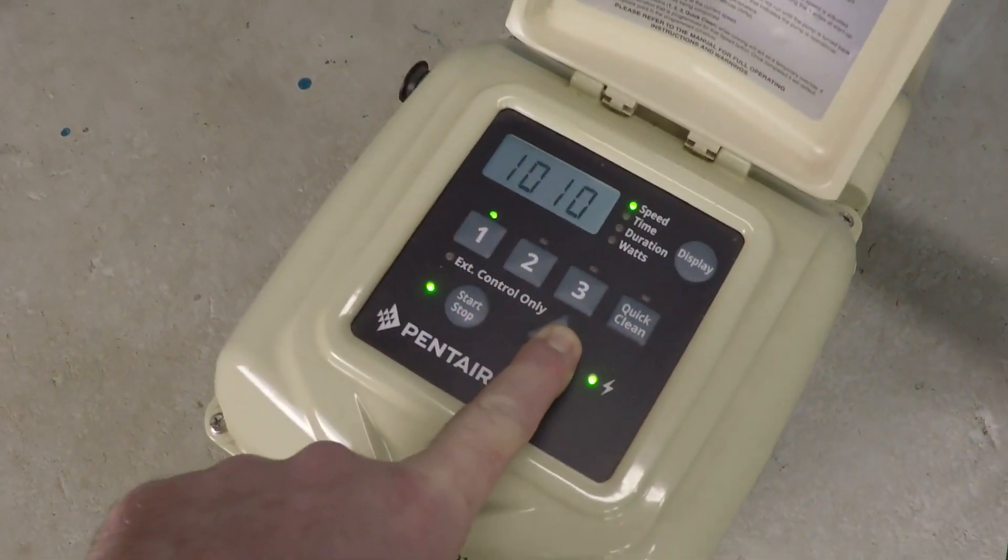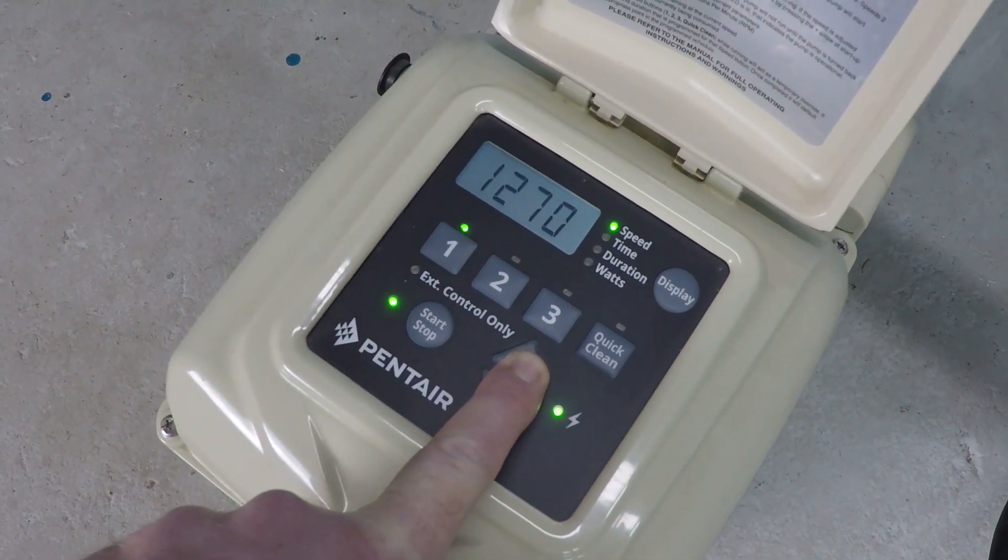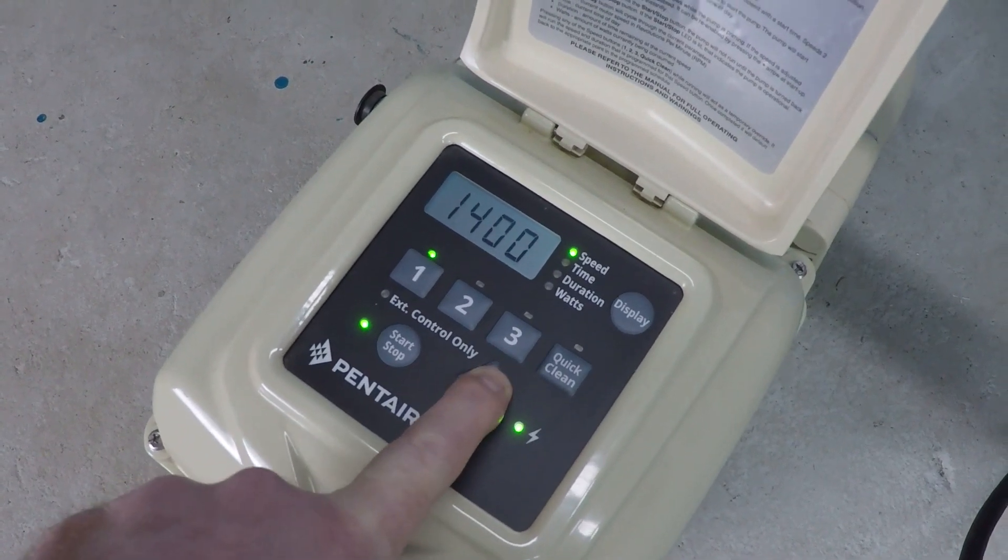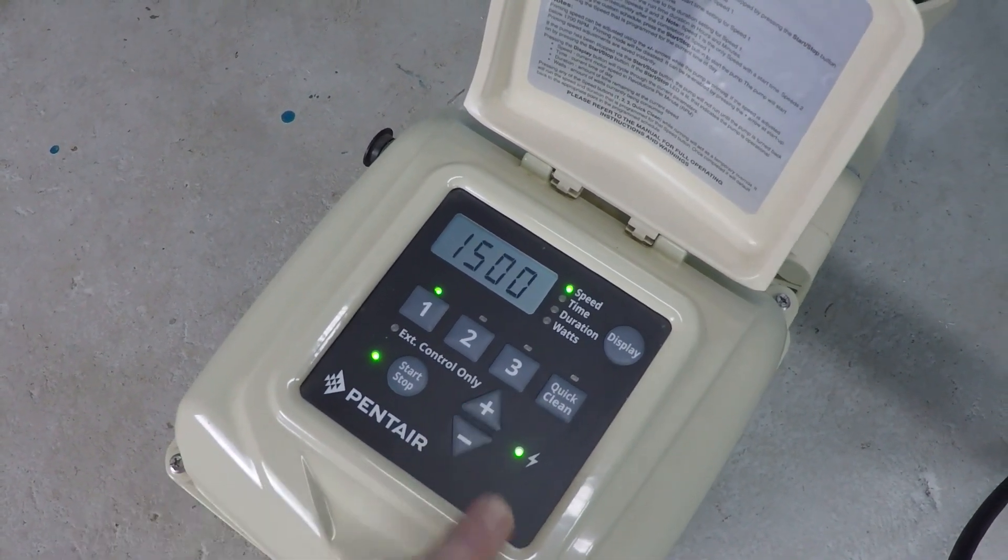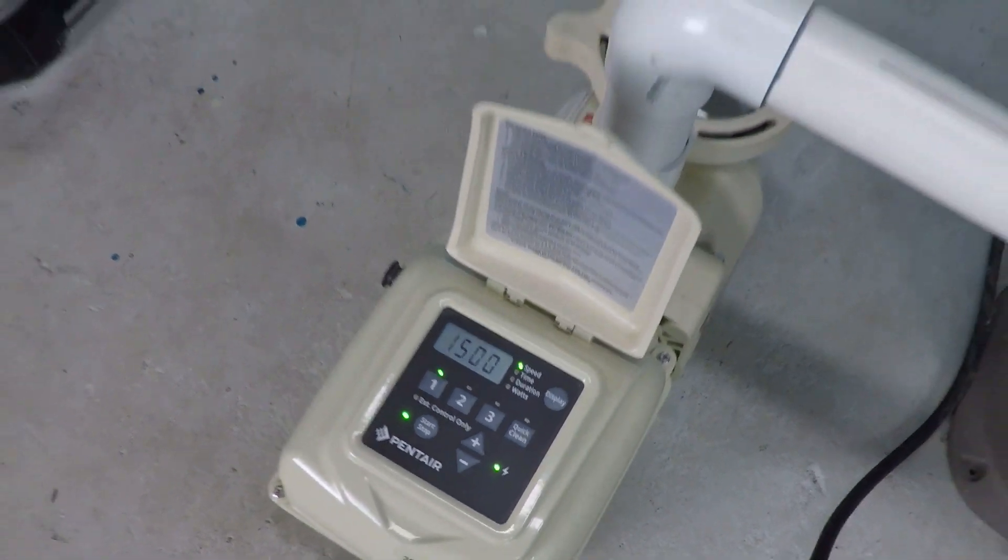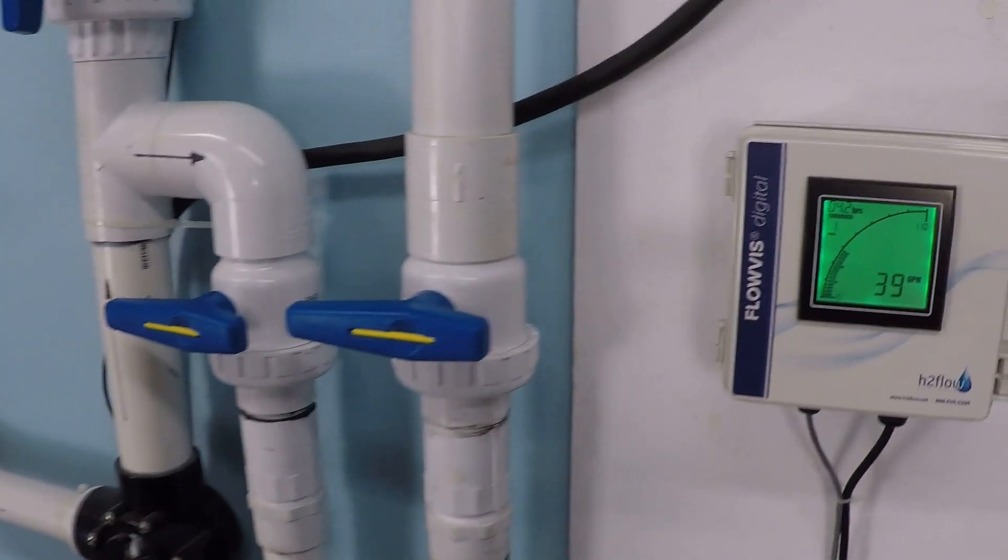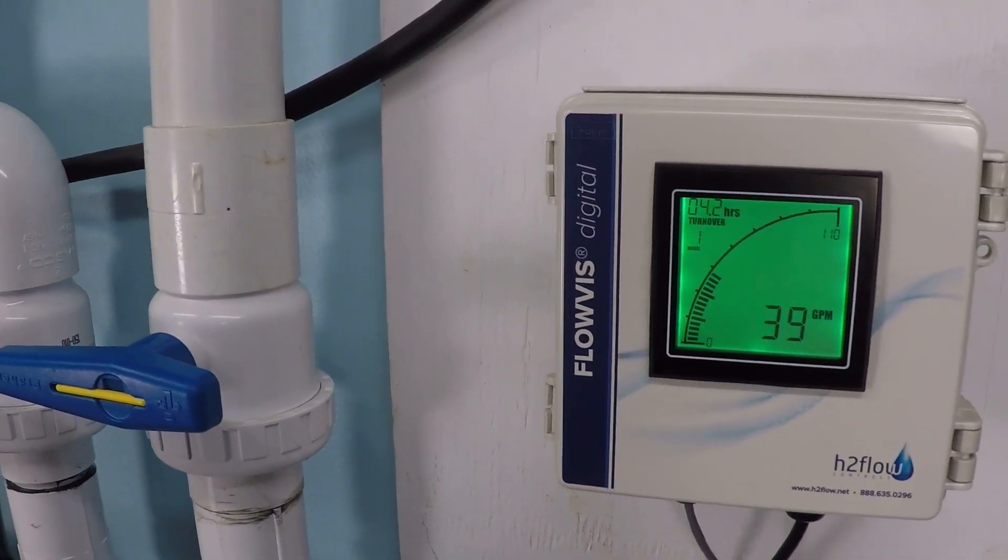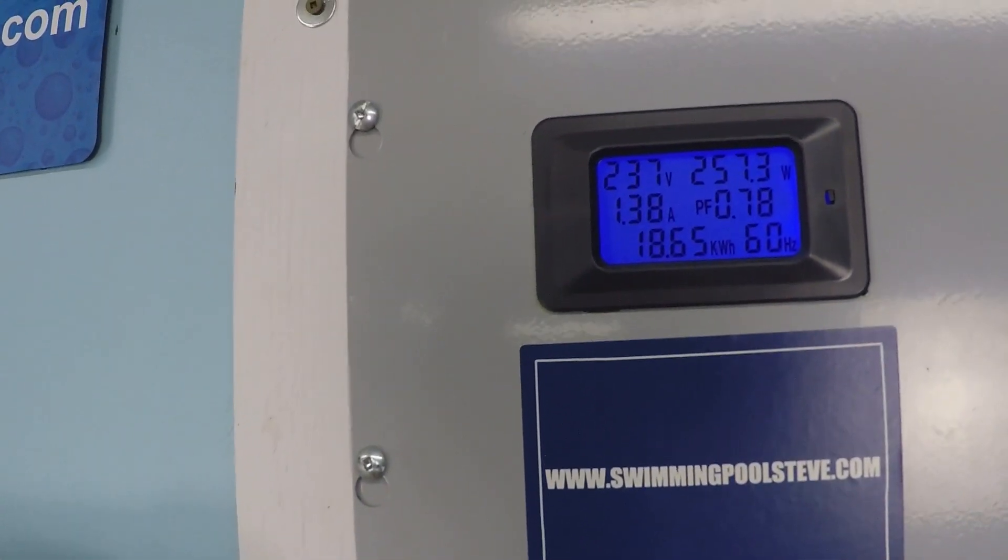We're not going to test all the numbers, we're just going to do kind of a spread here so we're going to jump up to 1500 now. Just shy of 40 gallons per minute there. 257 watts power consumption.